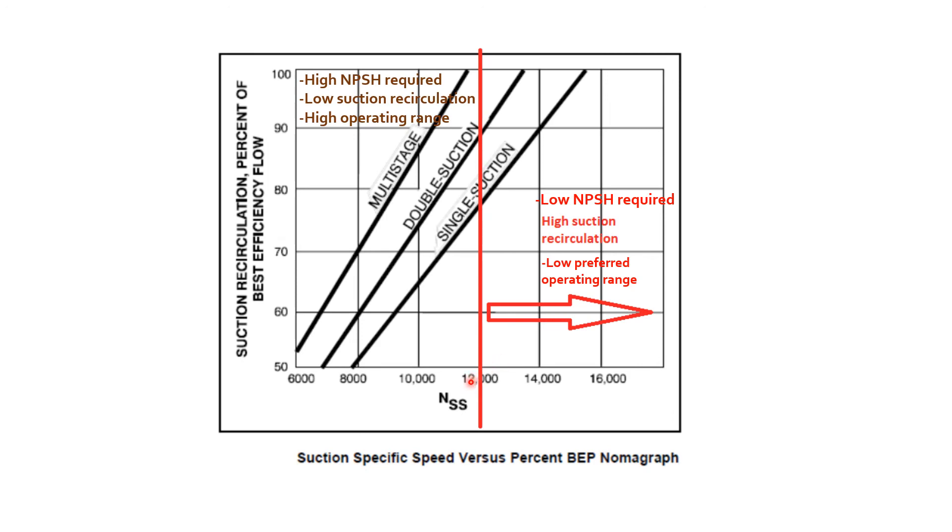In industry, there is a recommended parameter that pump suction specific speed should not exceed 12,000 NSS. Why is this set in the industry standard? This can be explained through a chart showing the relationship between NSS versus percent best efficiency point.